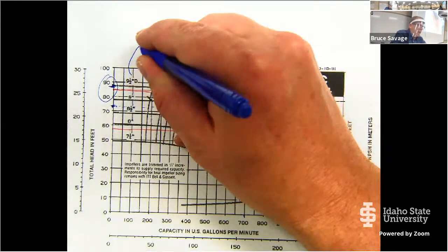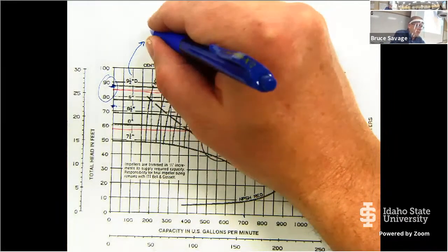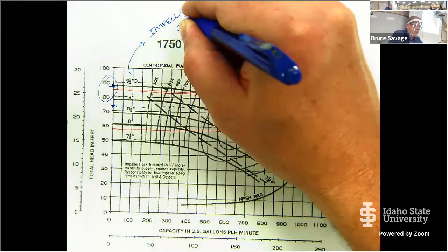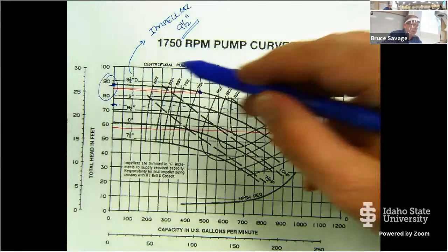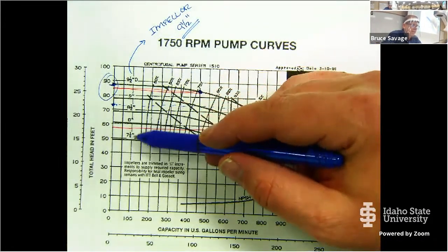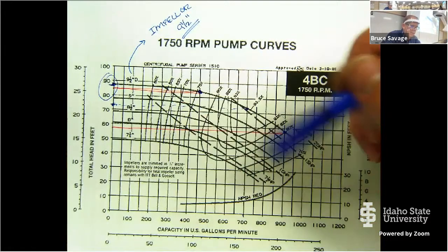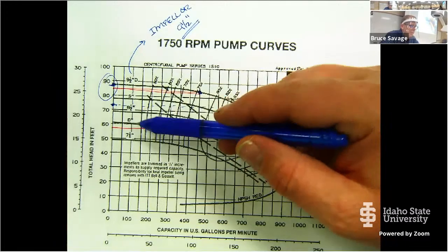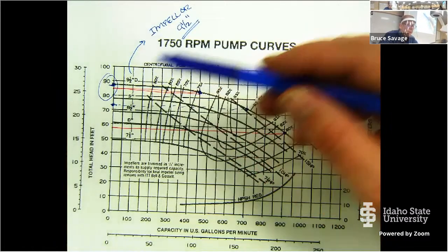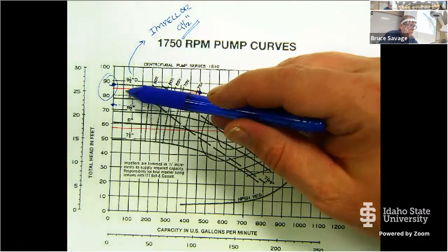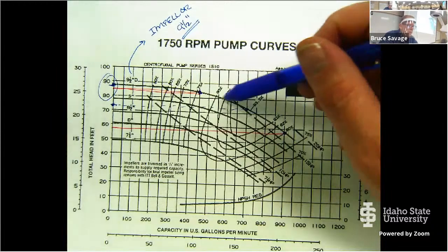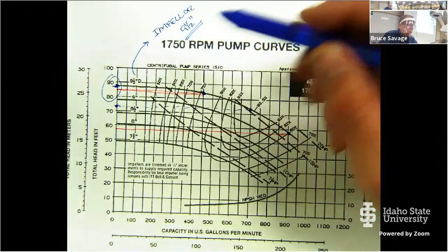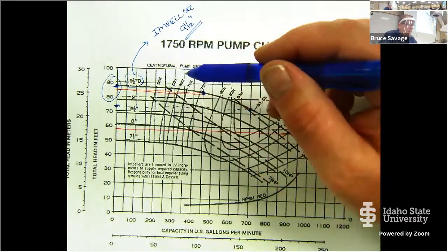So based off the efficiency? I said, no, the top curve, this is with an impeller that is a 9.5-inch impeller. So this pump can have a 9.5-inch, 9, 8.5, 8, 7, should be 7.5. Somewhere it says right here, impellers are trimmed to quarter increments. So you could do a bunch more in there as well. If you wanted to do like a 9 1/4, you could trim 9 1/4, and you just interpolate your pump curve in between.